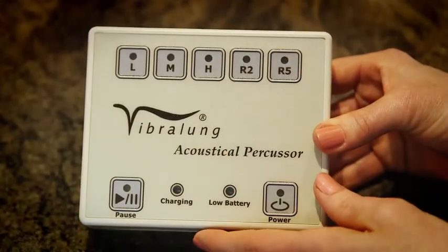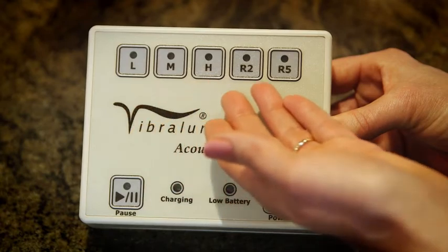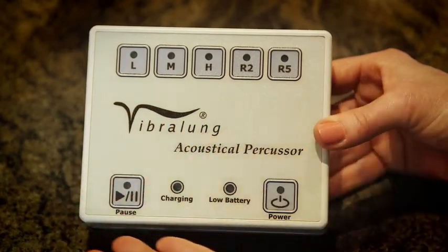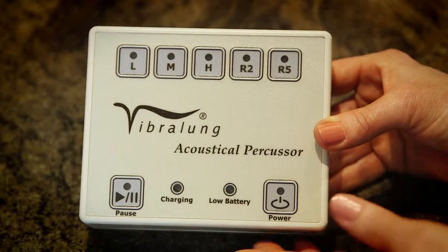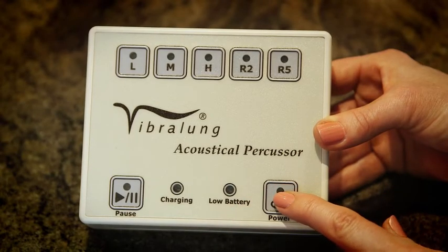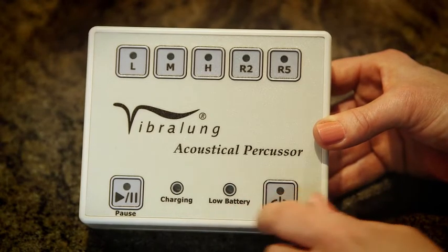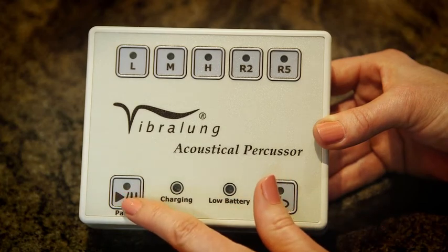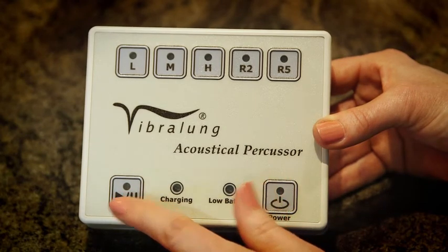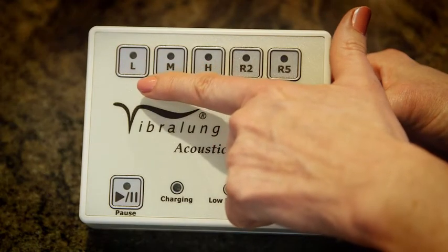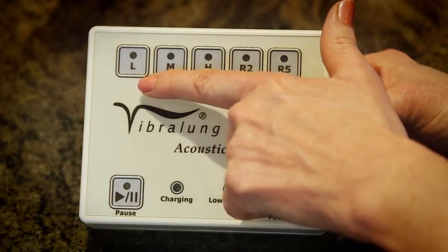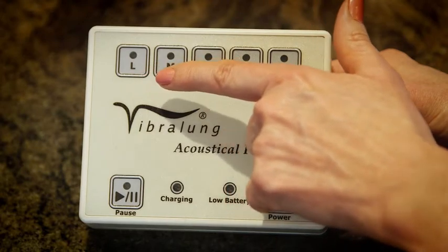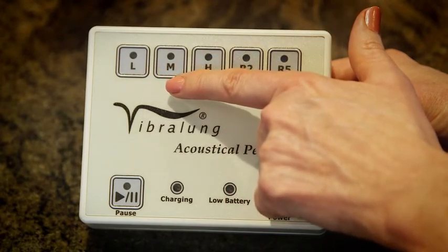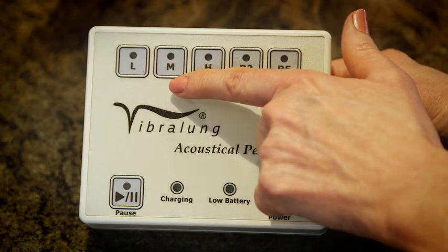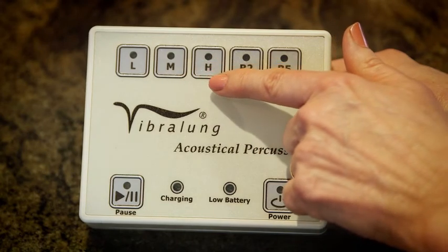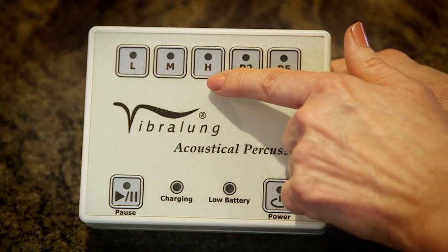There are 7 user-selectable button settings on the treatment control unit that illuminate when pressed. Press the power button setting to turn the treatment control unit on or off. Press the play-pause button setting to start, pause, or resume a treatment session. The L button setting is for low-frequency treatment of 5 to 350 Hz. The M button setting is for medium frequency treatment of 5 to 660 Hz. The H button setting is for high frequency treatment of 5 to 1200 Hz.